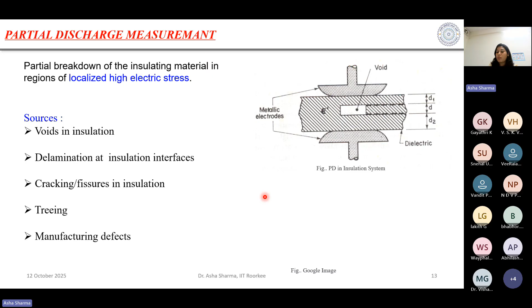If I have two electrodes, and these two electrodes are completely shorted by some current, we say complete breakdown. But if they are not shorted by current, but there is a discharge somewhere in between these two, we say it is a partial discharge. Let's say this is some insulating material which I am considering. Again, this is some high voltage which I have applied. This system is grounded. You can imagine it's the same thing for the insulator string. So let's say this is my insulator string, high voltage is there, ground is there. If there is something which is causing the partial discharge, it may cause the complete breakdown.